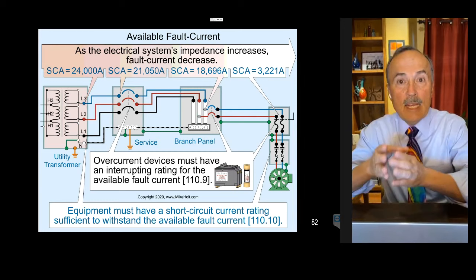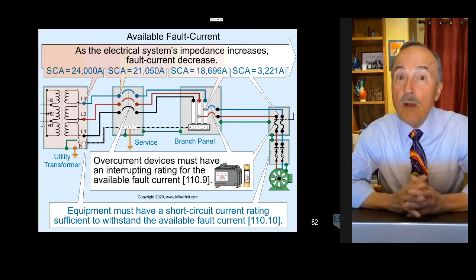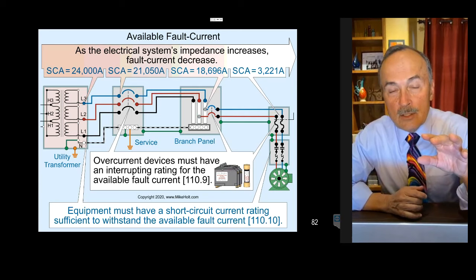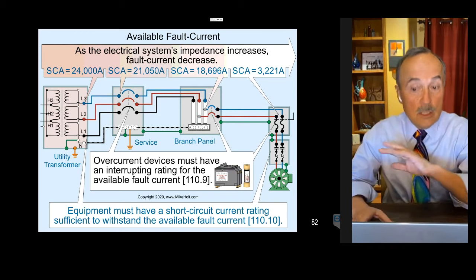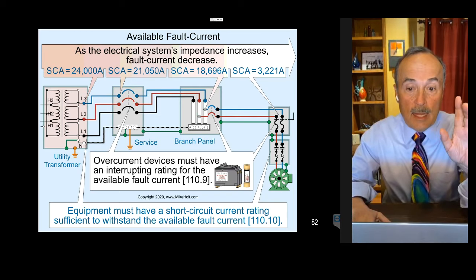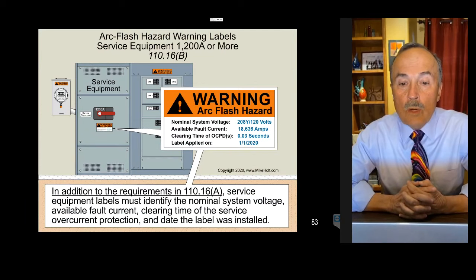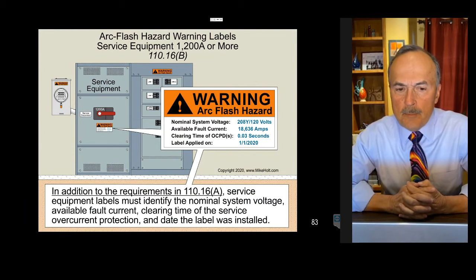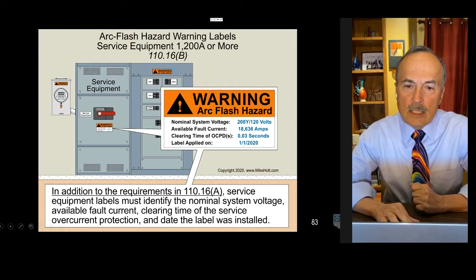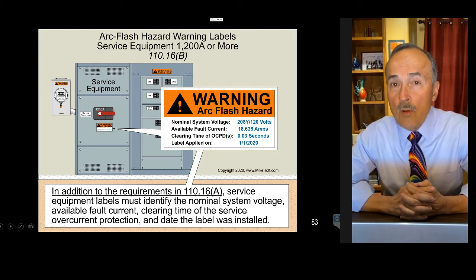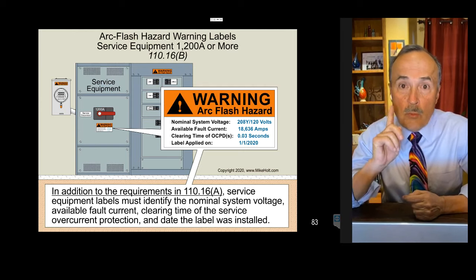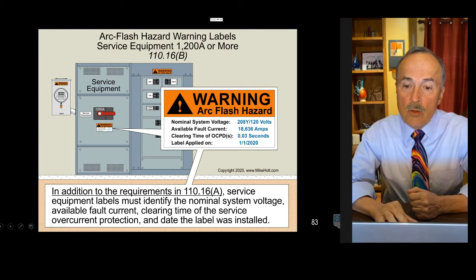The available fault starts at the power supply. Now, if you have a solar PV system, obviously it's limited because it's not like a utility with a huge amount of power. But that available fault keeps decaying as you continue cascading the system. But you know why? Because you keep adding reactance to that fault. And that's what it is. That's all covered in theory. All right. That was just a concept of that.